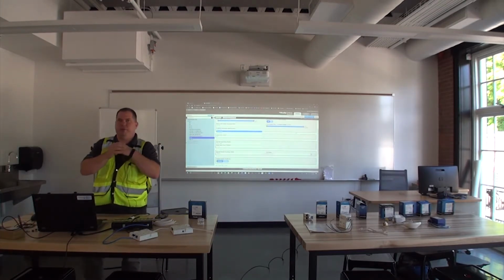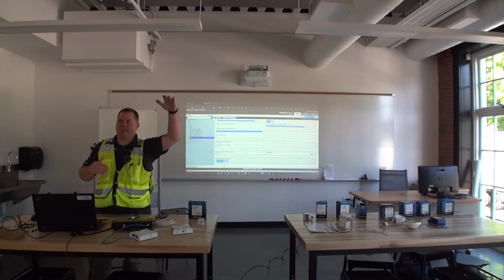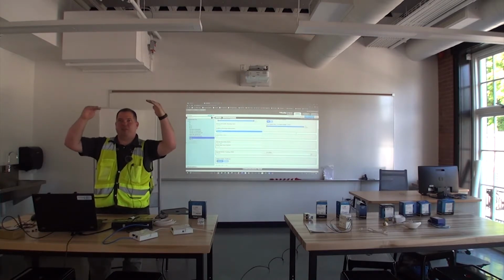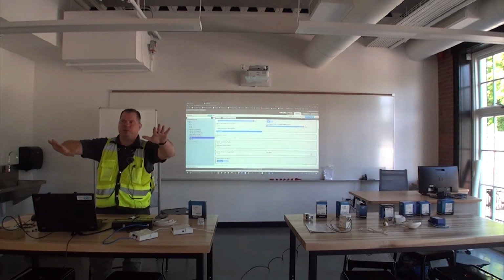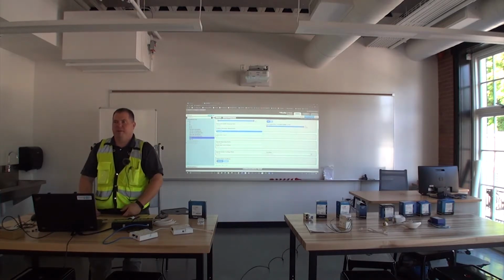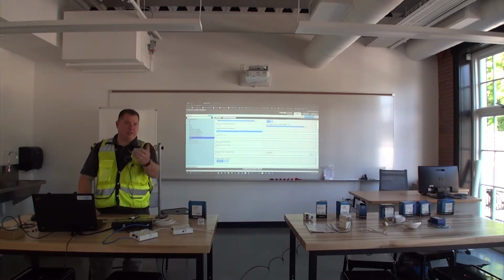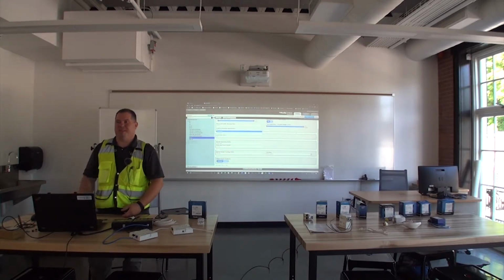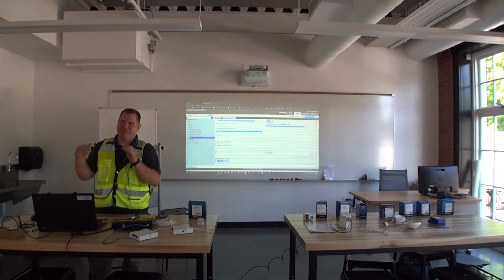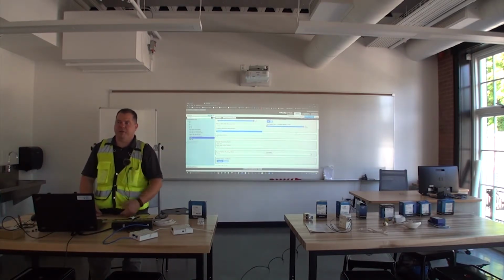It's because when we do daylighting, we don't want the daylight to permanently dim the daylight zone. We want the behavior to be consistent among the whole zone, so we turn the whole zone to temporary. But a lot of office spaces, like the principal's office, like permanent dimming because they like their setting to always come back to that bright level. So as long as it doesn't have daylighting in it, we leave it as permanent for that reason.